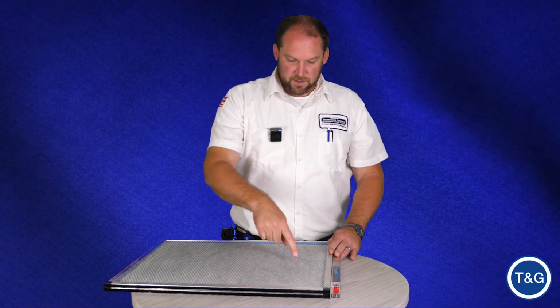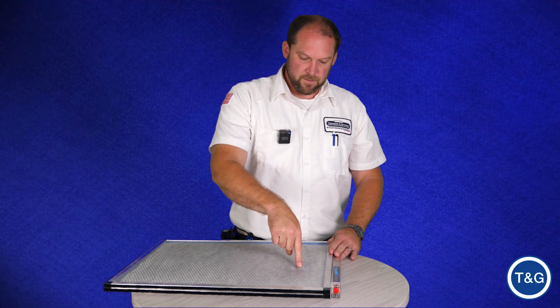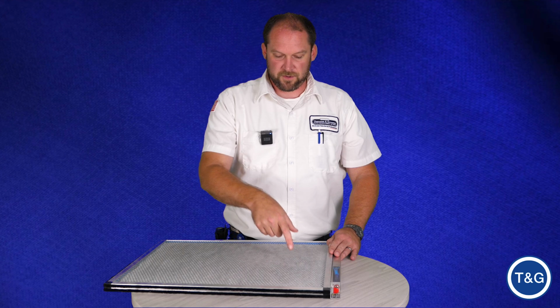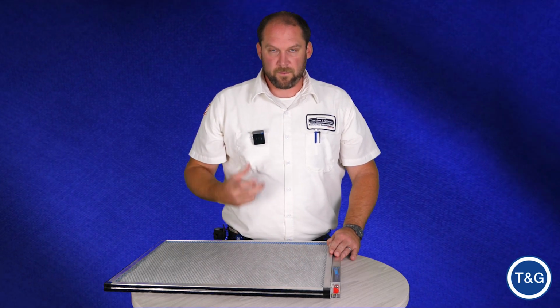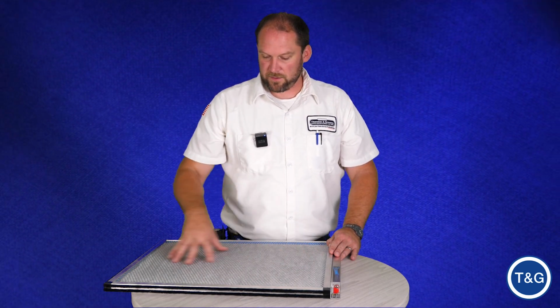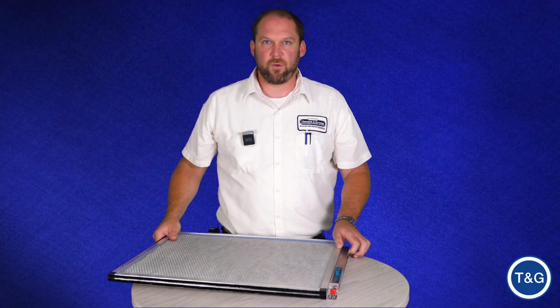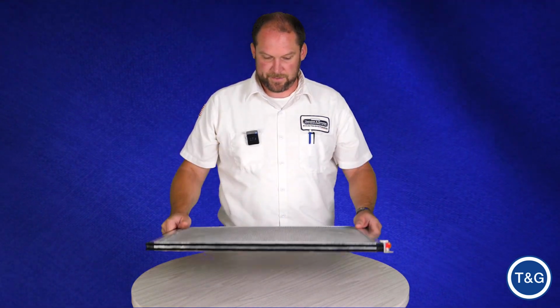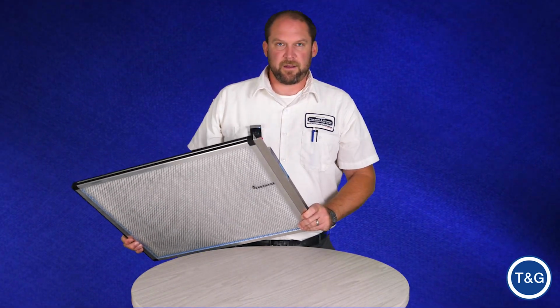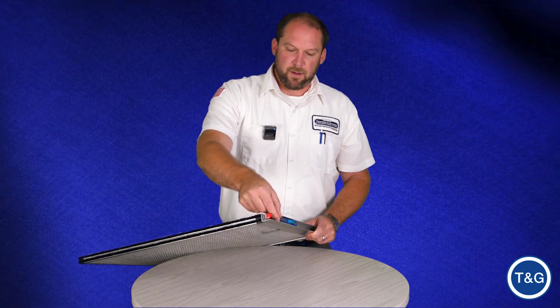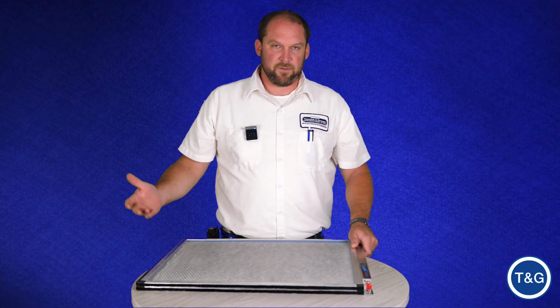Then you push on this little disc here, and you'll hear a click where that probe actually punctures the foil pad so the electrical current can travel through the whole filter and energize it. Once you do that, slide it back in like you took it out, and plug it in. Make sure you get that red light—if you've got a red light, you're filtering the air.